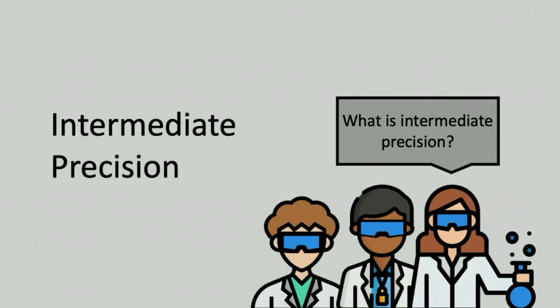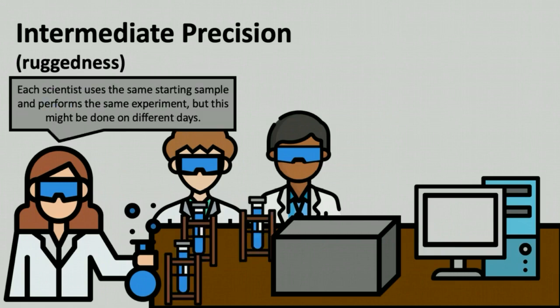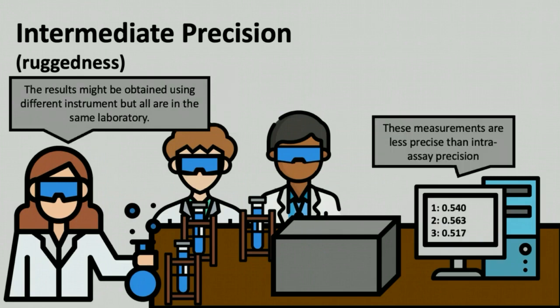The third type of precision is intermediate precision. Intermediate precision is sometimes called ruggedness and quantifies how reproducible a measurement is when an experiment is performed multiple times within the same laboratory. To determine intermediate precision, different scientists working in the same laboratory perform the same procedure using aliquots from the same sample. However, they might perform the experiment on different days and might also use different instruments to make the same final measurements. Because there are even more sources of variation in this setup, intermediate precision is often called ruggedness and is expected to be higher, or less precise, than intraassay precision. This is important for laboratories with many scientists and multiple instruments where it is unlikely that the same person or same instrument will be used for all of one type of analysis.